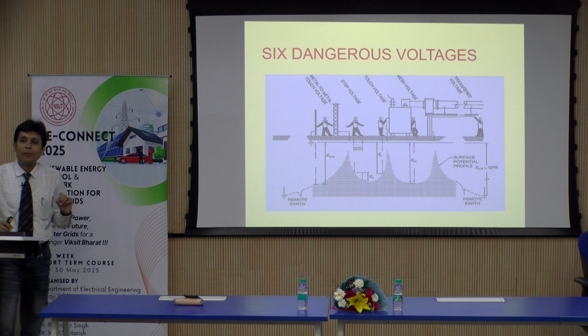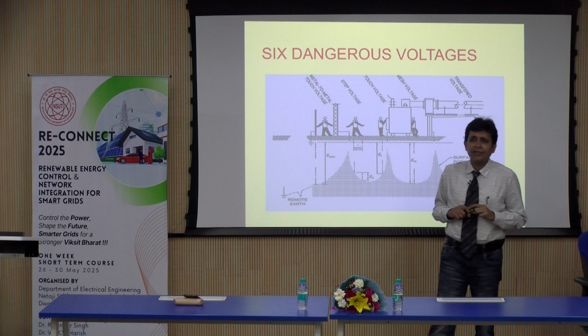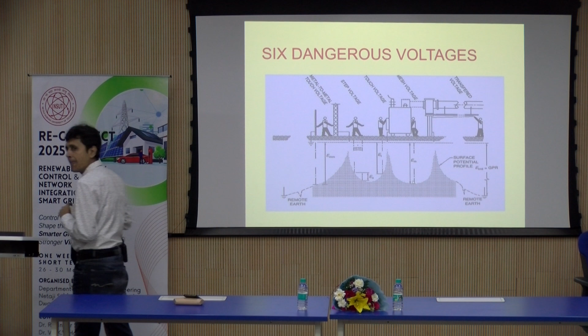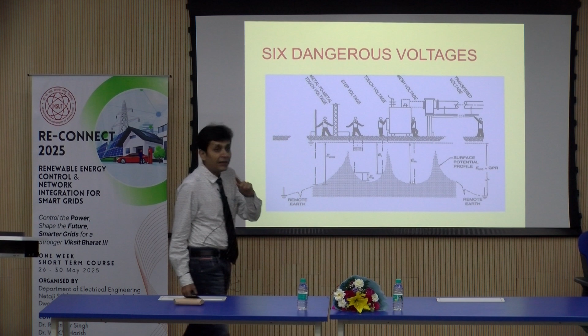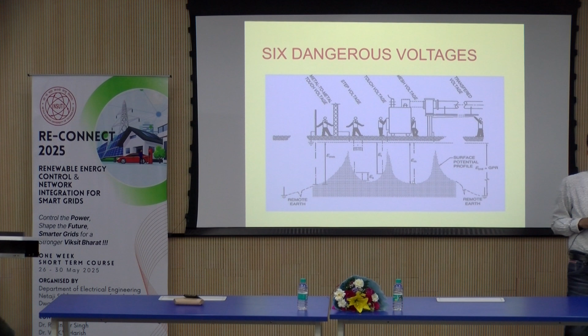In that category, the very first dangerous voltage is the step voltage. Then come the mesh voltage, touch potential, GPR, and transfer potential. If you don't have fundamental knowledge about the potential you are going to come across, and you are not paying full attention while designing your systems, because of voltage, there will be electrocution, there will be failure of assets, there will be fire that you can't stop.